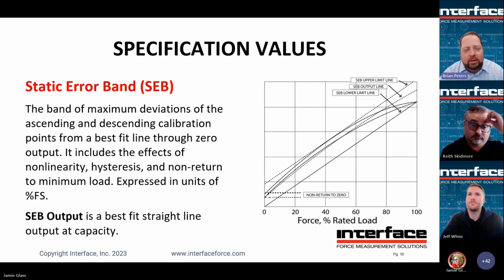All right, static error band. This is something not all sensor data sheets have. A lot of them do. This is a good way to look at a summary of performance for the load cell, because it takes into account the nonlinearity on the ascending side, the hysteresis value on descending, as well as non-return to zero. So it's actually, as stated, an error band that encompasses all the deviation of output for that load cell in a test or in a calibration.